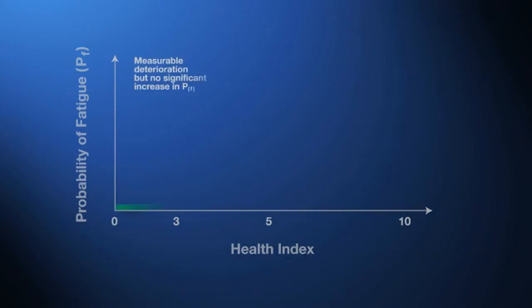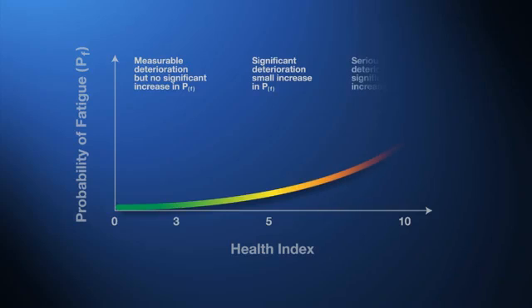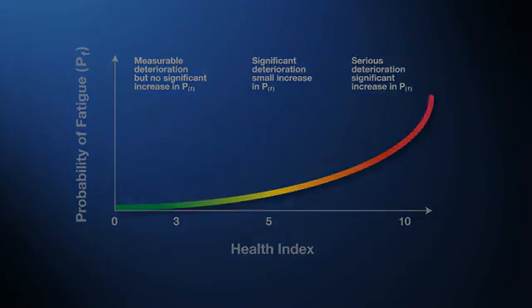We take all of the statistics, oil and gas data analysis, of asset inspection on site, performance and historical rating of how the transformer has been used, and then put that through an advanced statistical analysis process to then give you an idea of the risk of failure of your transformer compared to the rest of the fleet of your transformers, and ultimately even give you an idea of the life or the remnant life of the transformer itself.